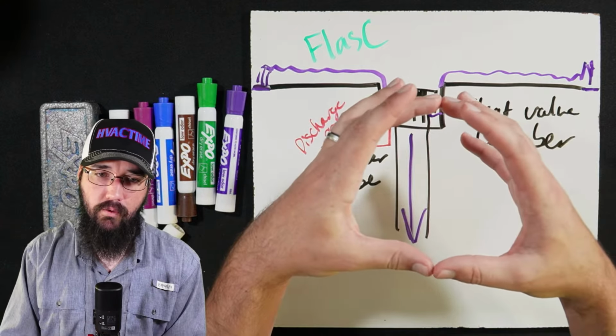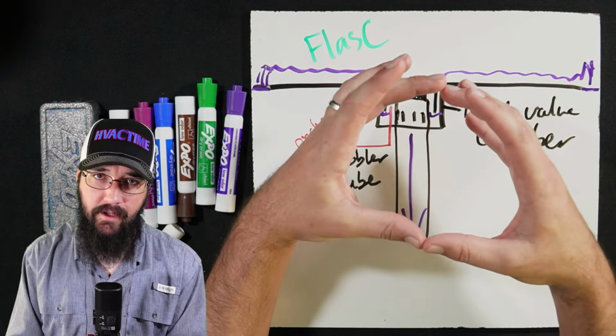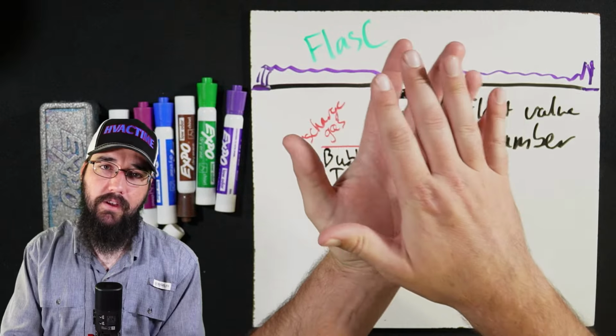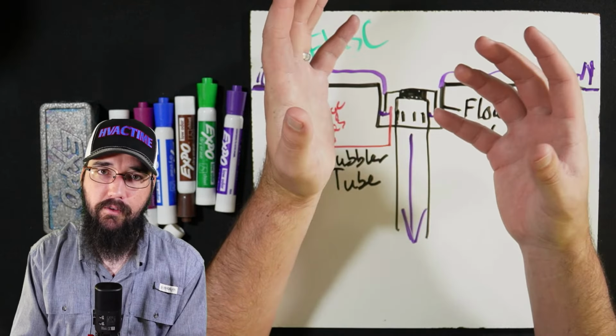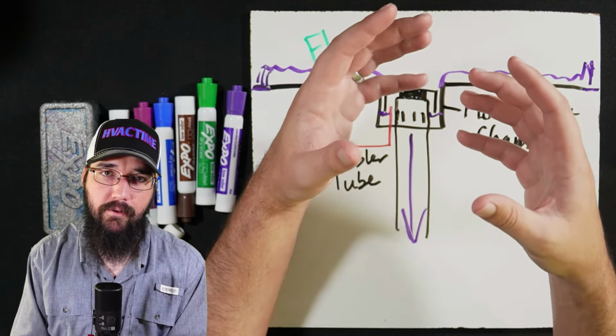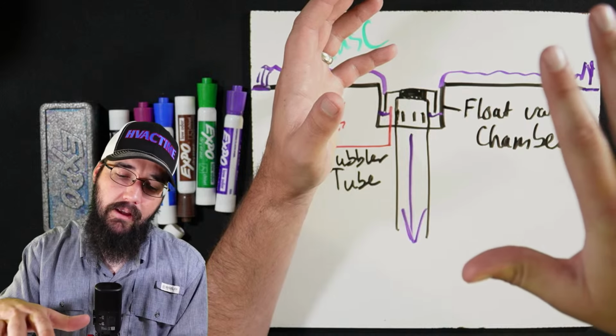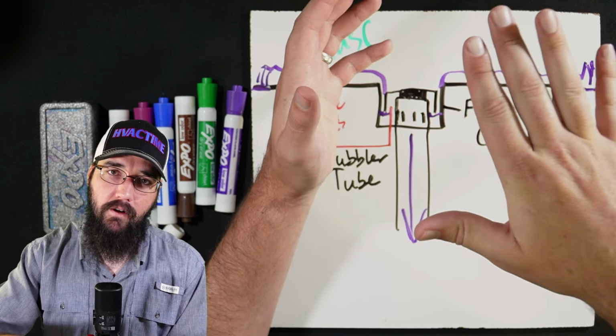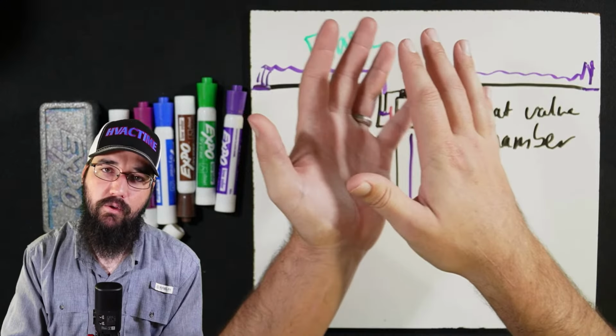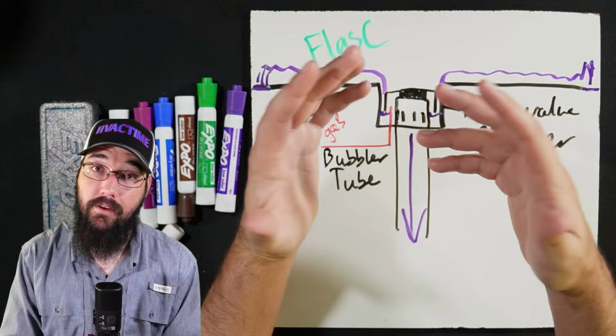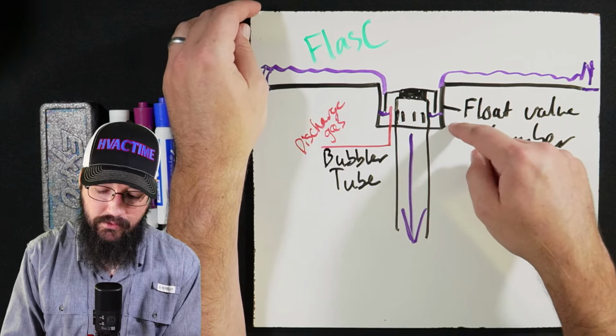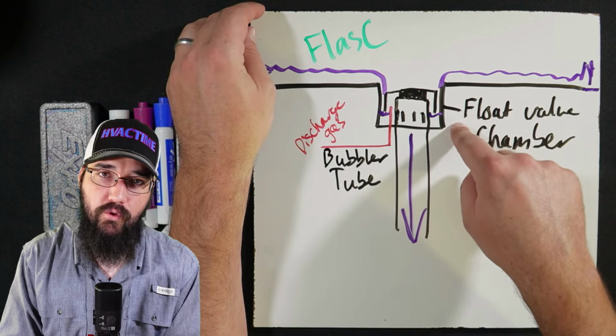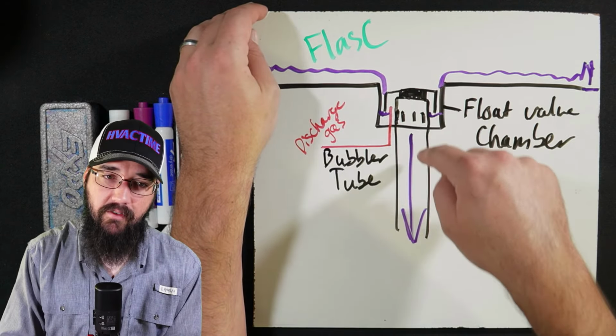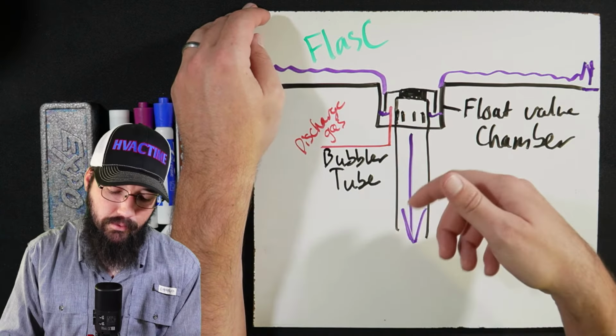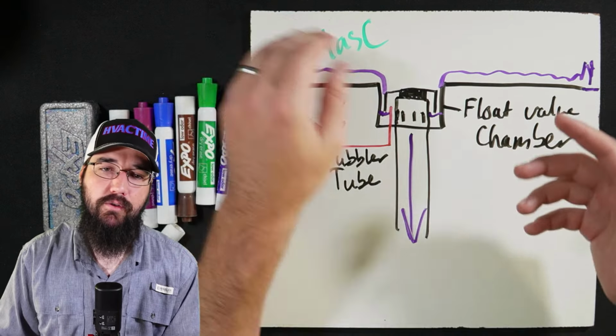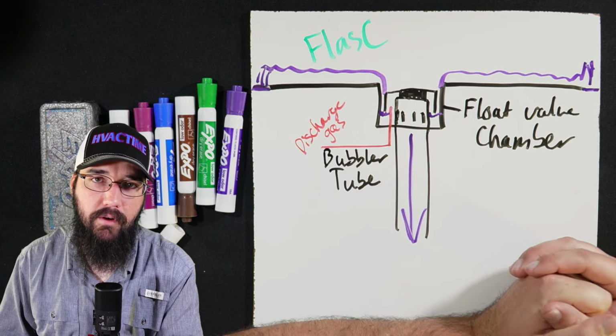That whole bowl is a pocket of vapor moving up and down just like that cup would. You can do this experiment yourself. If you haven't seen this kind of thing before, get a bucket or a bowl of water with an empty cup, make sure it's got air in it, tip it upside down, put it on the water, and try to push it down. You can feel the resistance, and you'll see the cup spring back up to the top of the water level. That whole process is how we're getting this valve to control. And then from there, it flashes off and meters down, and low pressure refrigerant, or lower pressure at minimum, leaves the metering valve, and we now have controlled flow going into the next phase of the process.